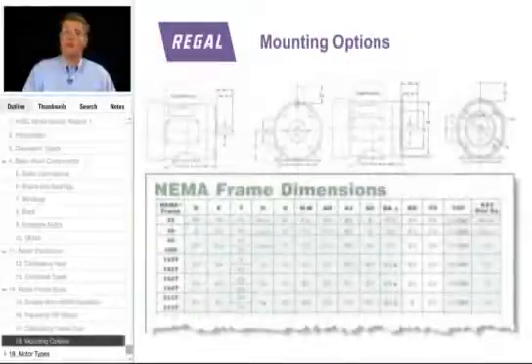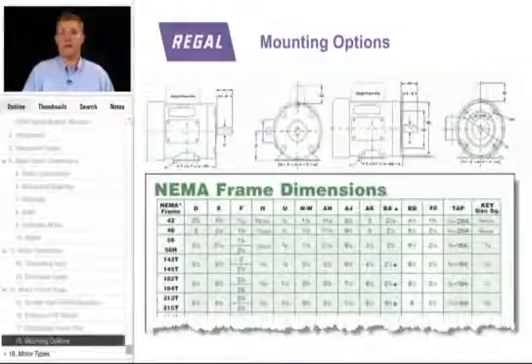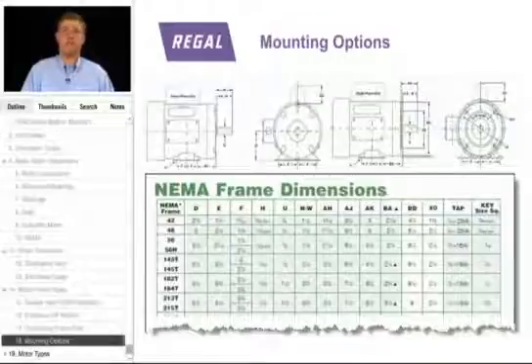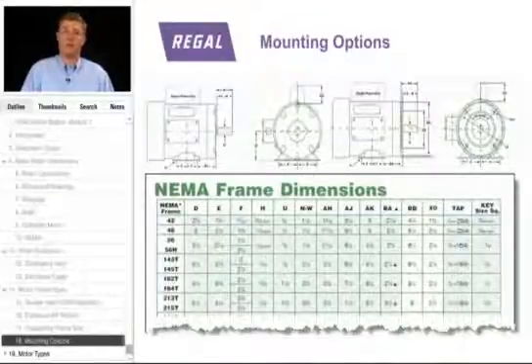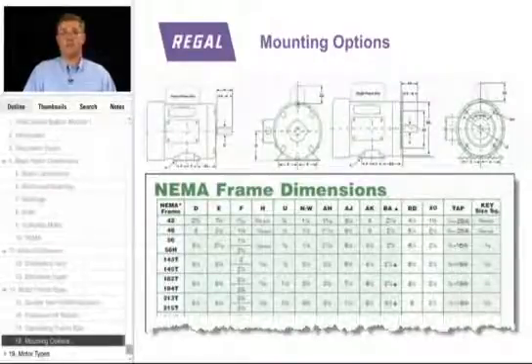The third digit in the NEMA T frame motors tells us the distance between the mounting foot holes in the bottom of the base. So it is possible to switch frame sizes if you understand where the center of shaft is. On T frame motors, a 143 T or a 145 T frame may be used if the motor is punched for the holes in the bottom of the base.